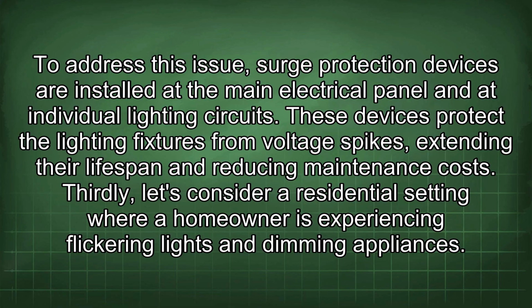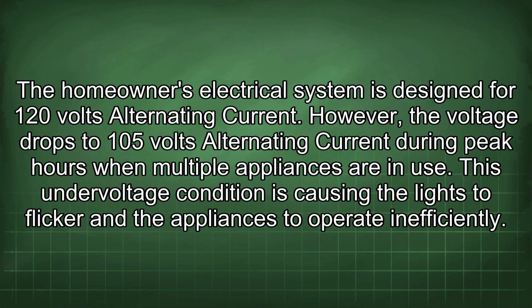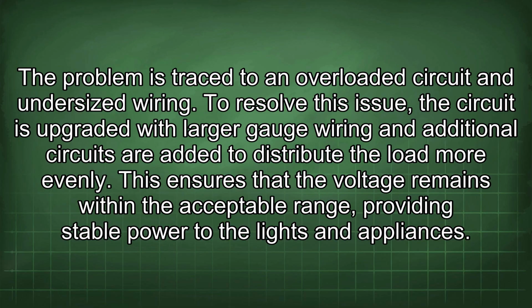Thirdly, let's consider a residential setting where a homeowner is experiencing flickering lights and dimming appliances. The homeowner's electrical system is designed for 120 volts alternating current. However, the voltage drops to 105 volts alternating current during peak hours when multiple appliances are in use. This undervoltage condition is causing the lights to flicker and the appliances to operate inefficiently. The problem is traced to an overloaded circuit and undersized wiring.